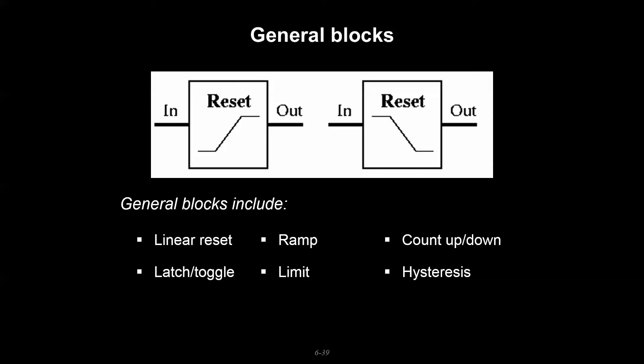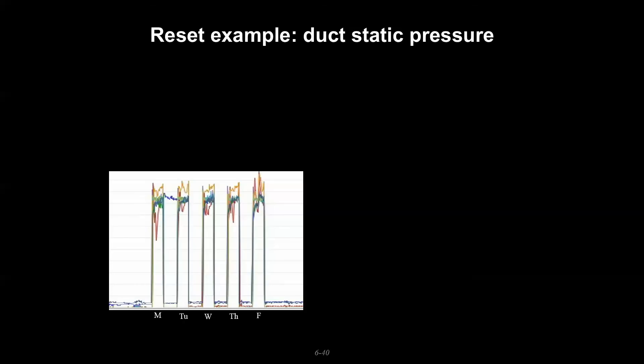Or a hysteresis block which is essentially accounting for some one-way differential as you approach a state change. Here's an example we talked about: duct static pressure in the air side system. Oftentimes a designer sets the duct static based on the worst condition - often your design cooling. How much pressure do you need to move the CFM to all of your boxes and keep everybody happy and meet your design loads?